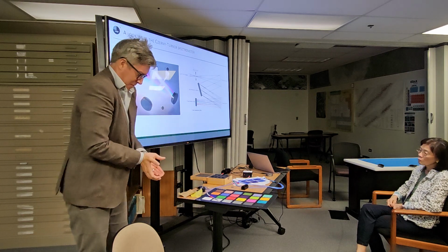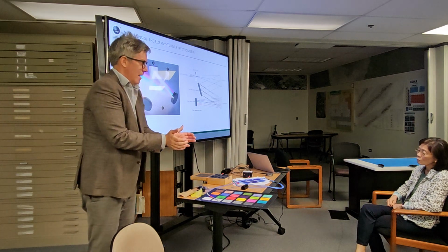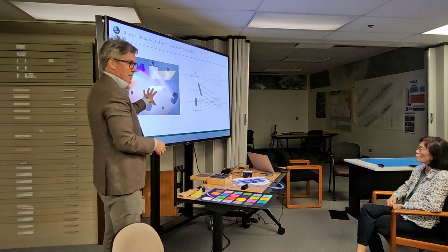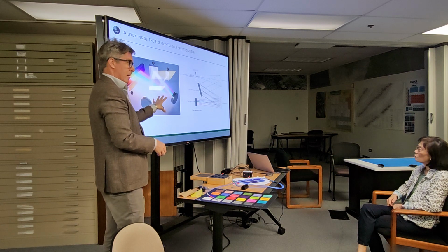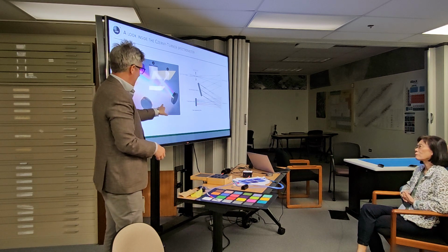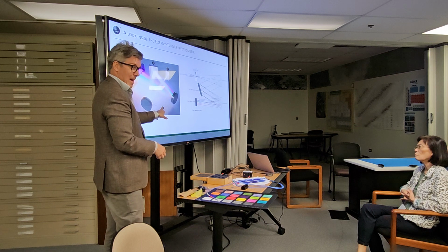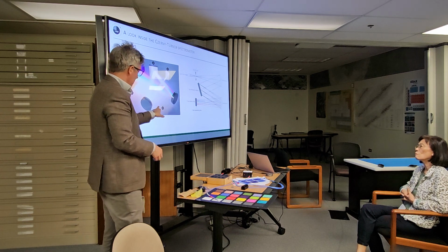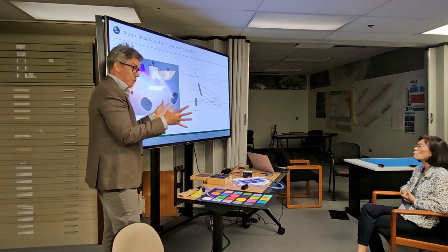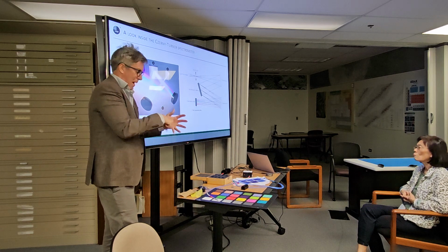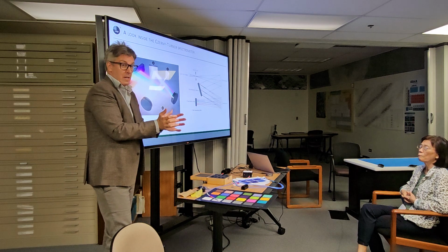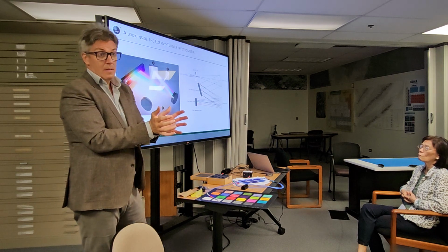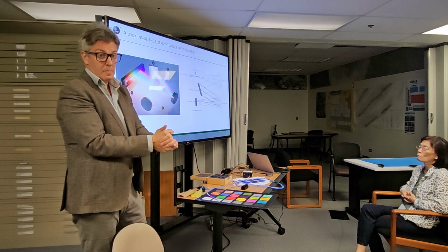So if you have a cup-shaped piece of black metal in there, and this is predicted, right? An optical engineer predicts likely ghost images or stray light. And if you say, well, there's going to be a load of light hitting this surface of the spectrometer, and some of that is going to bounce in, what you can do is put a cup-shaped thing here to trap those photons, get them bouncing around multiple times within the cup-shaped thing. And by doing that, you can create a cavity and no photons will escape.